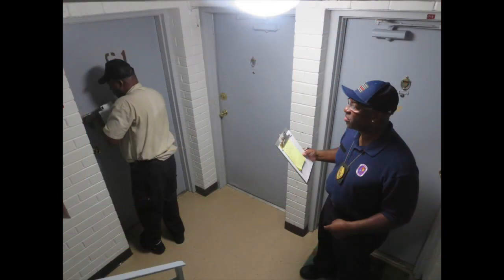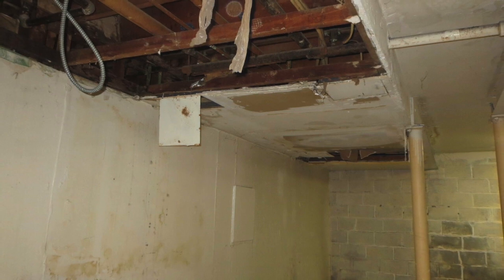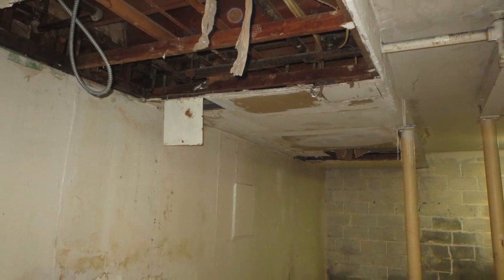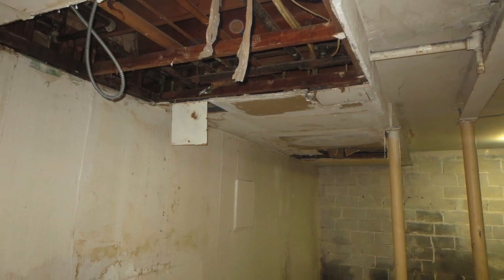Have the maintenance staff open the storerooms. Storage rooms should be locked and have a 1-hour rating or be protected by a sprinkler. If not, they should be 100% empty. Holes in the drywall as seen here must be repaired. Note these holes on your correction order.